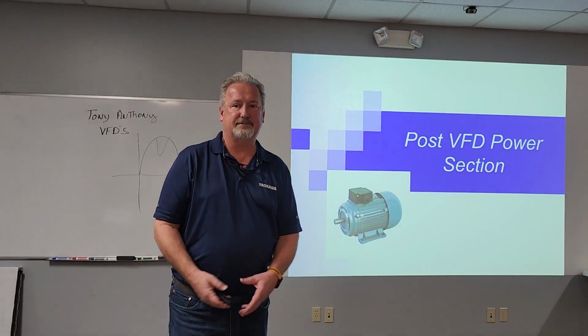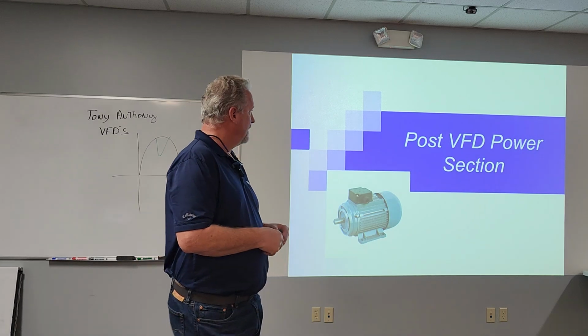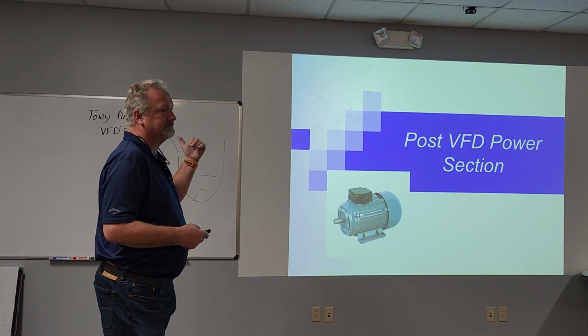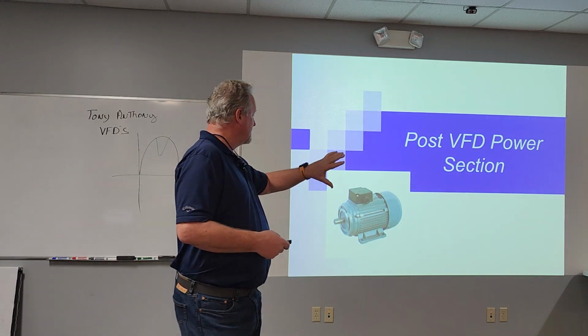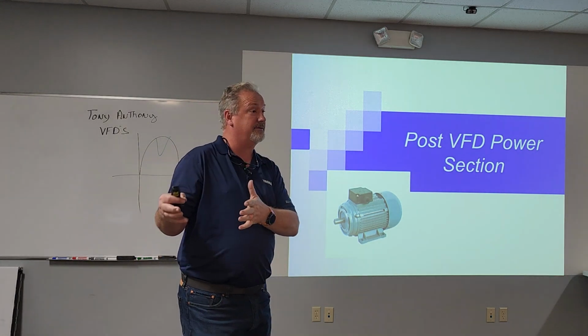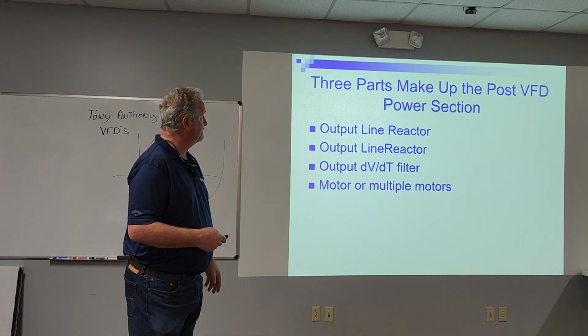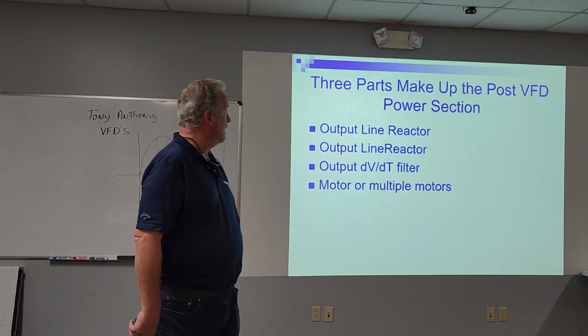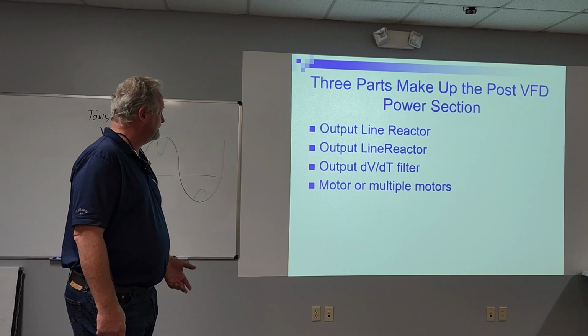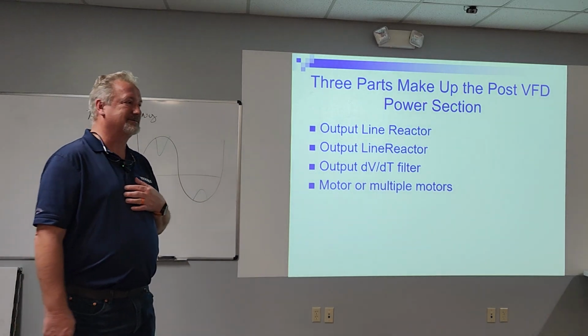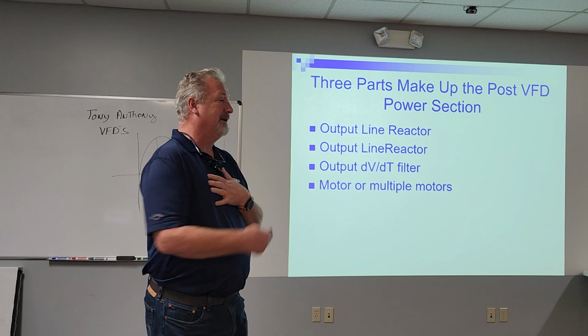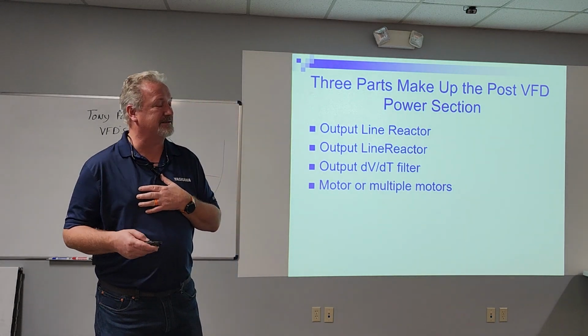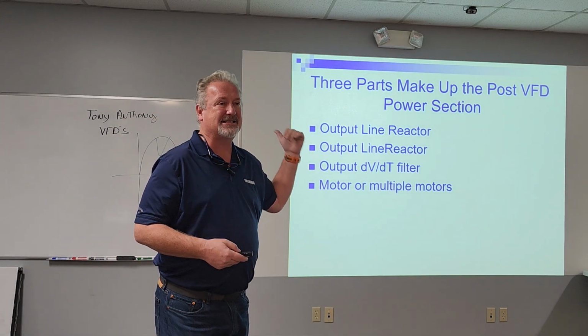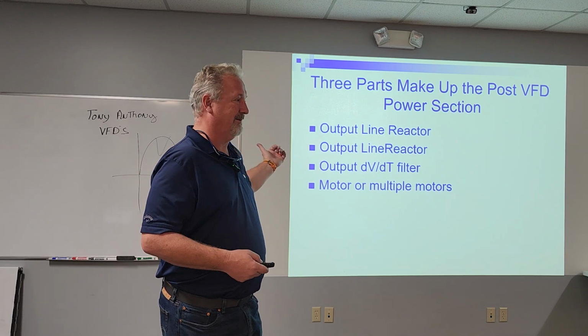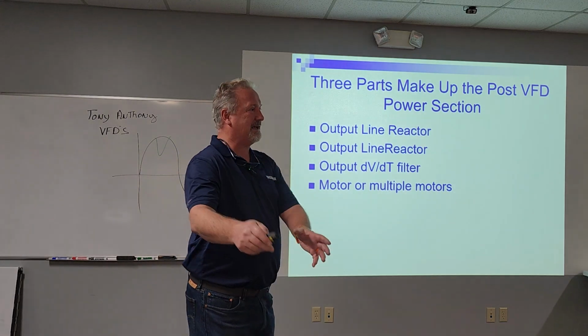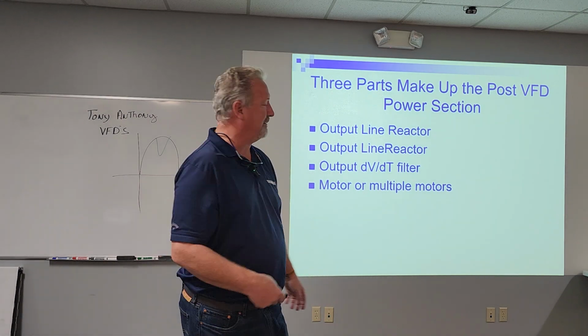Any questions on the drive? So we talked about what feeds a drive. We talked about the drive. Now let's cover what we may need after the drive, besides the motor, obviously. Yeah, between the drive and the motor. Most common thing we would have is an output line reactor. Normally we call it an output load reactor. This has been a misprint that I haven't fixed, and I like it. There's a reason I haven't, because it's the same exact thing we put on the input side. It's the same part. Remember, you take a line reactor, you stick it on the other side, the exact same thing. It's just doing a different job.